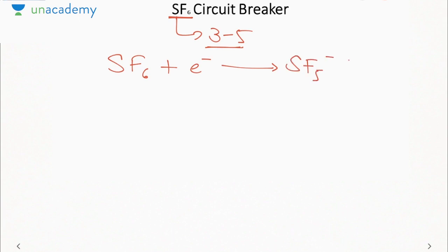Next type of circuit breaker is the SF6 circuit breaker. Here instead of air we will use SF6 gas, and SF6 gas is a better dielectric as compared to air. So it is 3 to 5 times better than the air blast circuit breaker. Why? Because the dielectric strength of SF6 is higher. How? When SF6 encounters the electrons coming due to the arc, because they create charged particles, it will become SF5 minus plus F. So what will happen is that SF6 is absorbing the electron, so it is reducing the number of charged particles between the plates of the circuit breaker. So that is how it has a high dielectric strength.